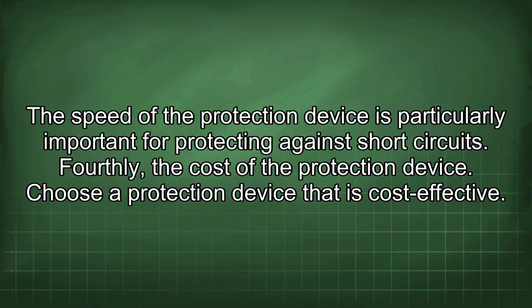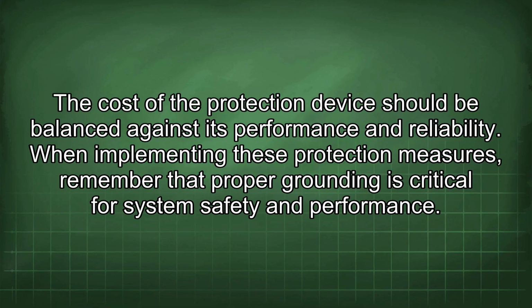Fourthly, the cost of the protection device. Choose a protection device that is cost-effective. The cost of the protection device should be balanced against its performance and reliability. When implementing these protection measures, remember that proper grounding is critical for system safety and performance.